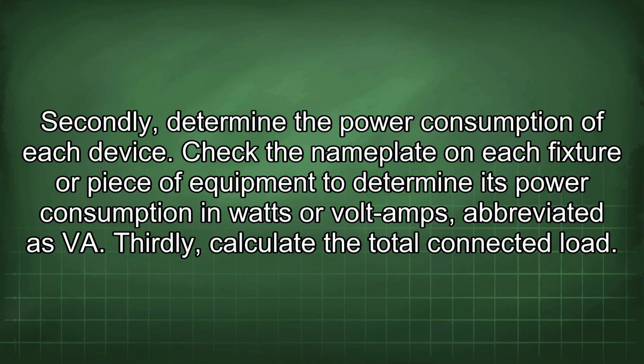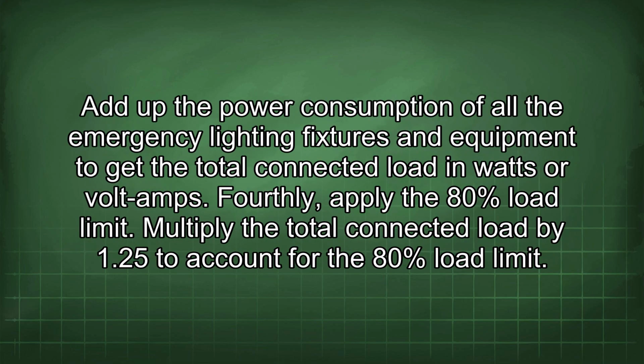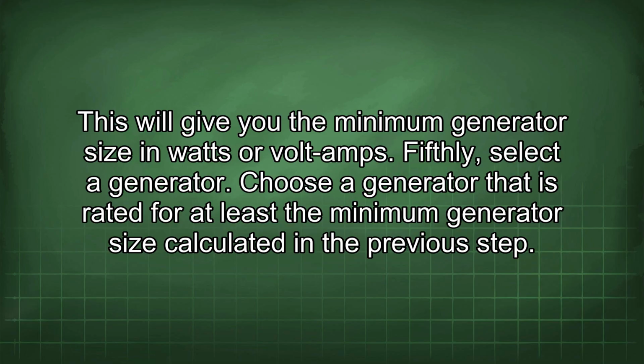Secondly, determine the power consumption of each device. Check the nameplate on each fixture or piece of equipment to determine its power consumption in watts or volt amps, abbreviated as VA. Thirdly, calculate the total connected load. Add up the power consumption of all the emergency lighting fixtures and equipment to get the total connected load in watts or volt amps. Fourthly, apply the 80% load limit. Multiply the total connected load by 1.25 to account for the 80% load limit. This will give you the minimum generator size in watts or volt amps.